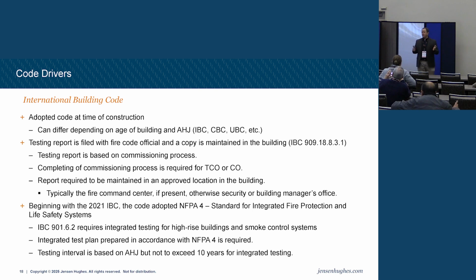So what if I don't have a fire command center? Sometimes with older buildings and remodels, there's no fire command center. Usually jurisdictions will let that slide. They'll say, okay, we don't need you, because a fire command center has to have a door to the exterior, has to be at street access, has to be on the fire department address side, all these requirements. It has to be a certain size. You may not be able to comply with that in an older building. You may already have all that exterior space committed, things like that.